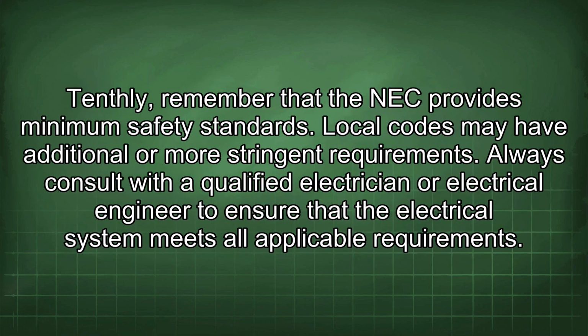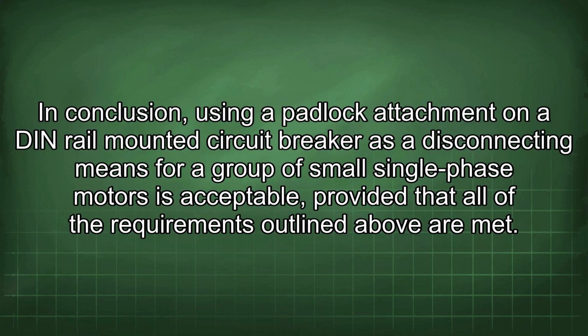Tenthly, remember that the NEC provides minimum safety standards. Local codes may have additional or more stringent requirements. Always consult with a qualified electrician or electrical engineer to ensure that the electrical system meets all applicable requirements. In conclusion, using a padlock attachment on a DIN rail-mounted circuit breaker as a disconnecting means for a group of small single-phase motors is acceptable, provided that all of the requirements outlined above are met.